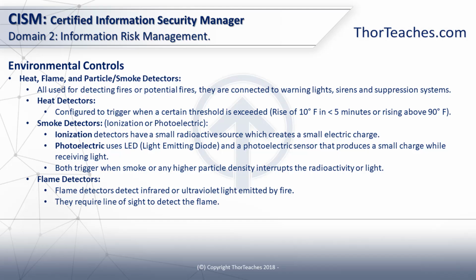And then finally we have flame detectors. They're not so commonly used, just like the infrared motion sensors. They detect infrared or ultraviolet light emitted by a fire. The downside to them is they need a line of sight to the fire.